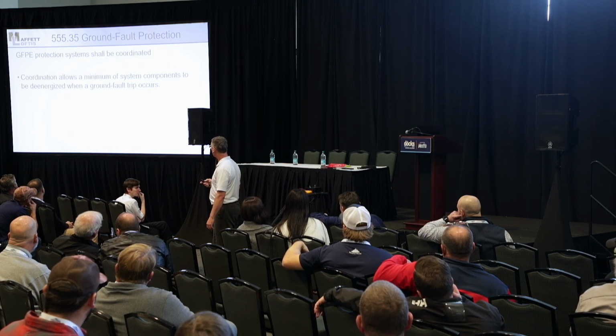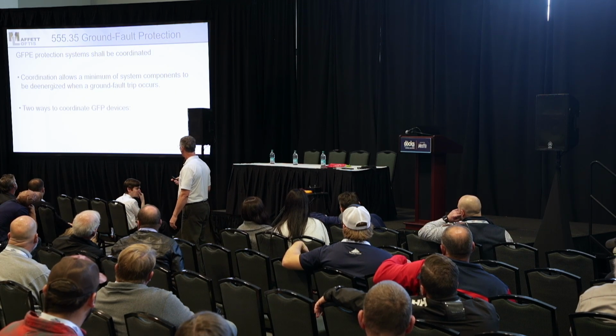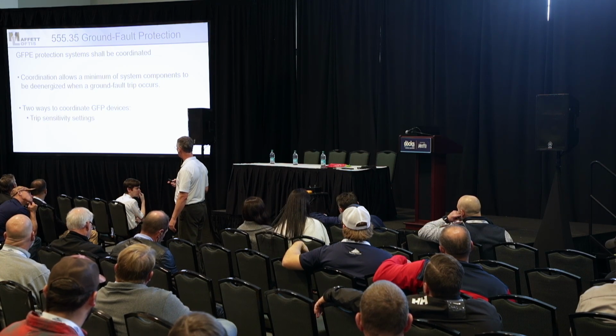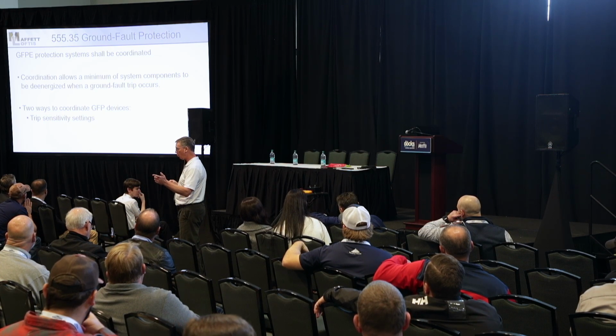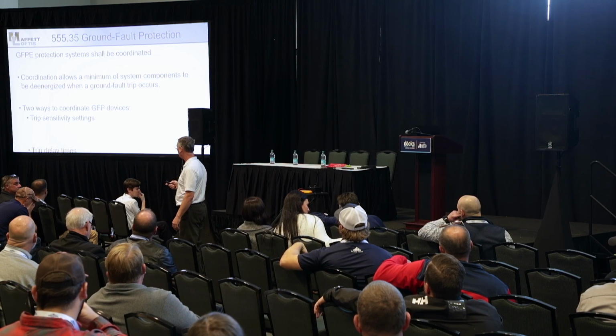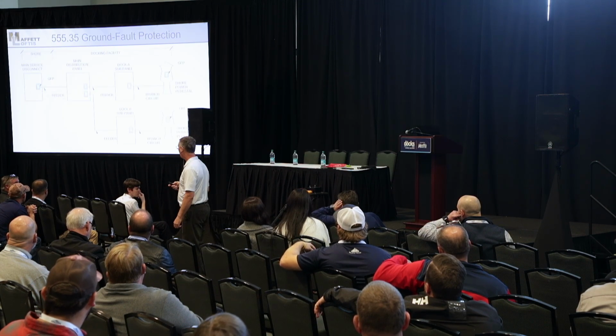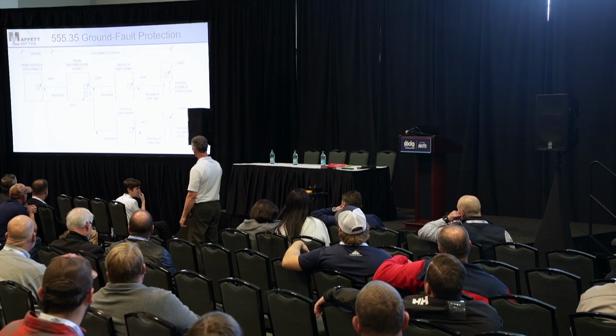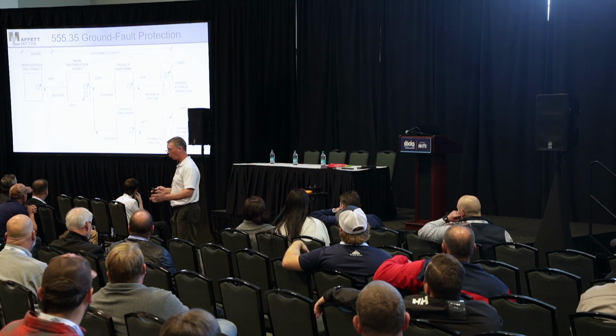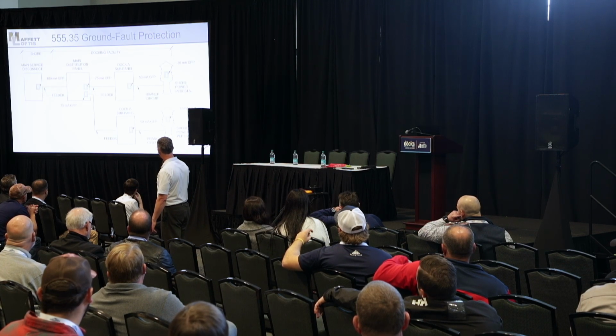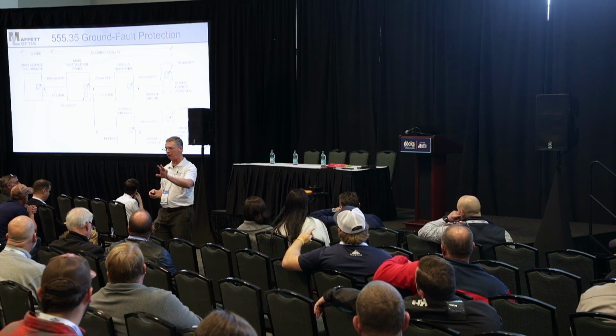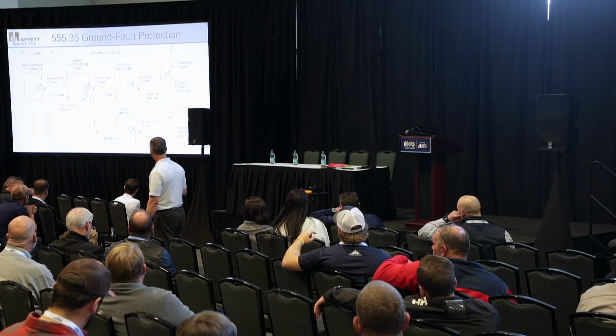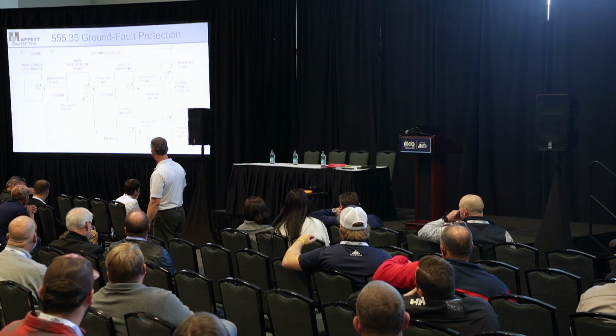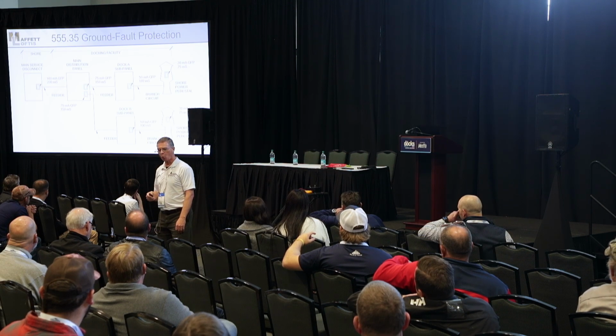If you go back and look, there are two ways to coordinate. One is the trip sensitivity levels at 30 and 50, but that doesn't always work because you can have boats that leak more current. But there are also trip delay times. For example, say I've got a lot of GFPEs in here for full coordination, and I've got 30 milliamp, 50 milliamp, 75, and 100 at those locations. I'm very limited in time, so I'm going to try to get through this. But if you set the times here, like something I have on the screen, and a bad boat comes in that leaks 300 milliamps, where is it going to trip now?